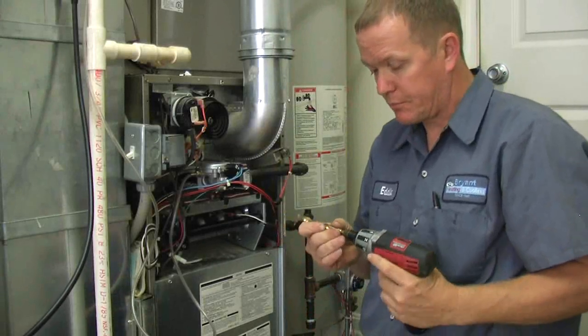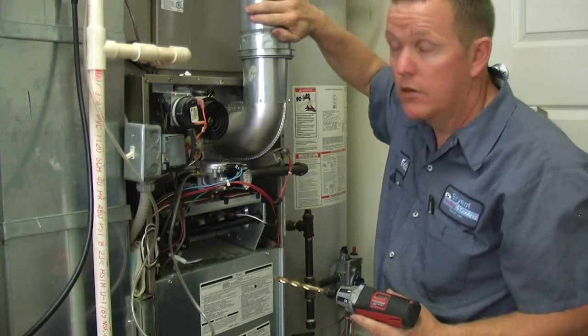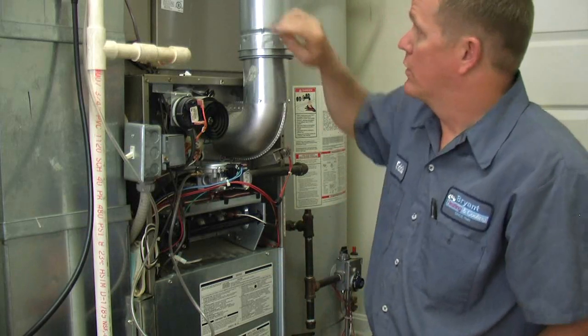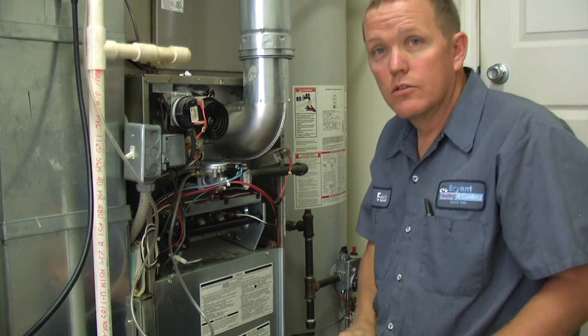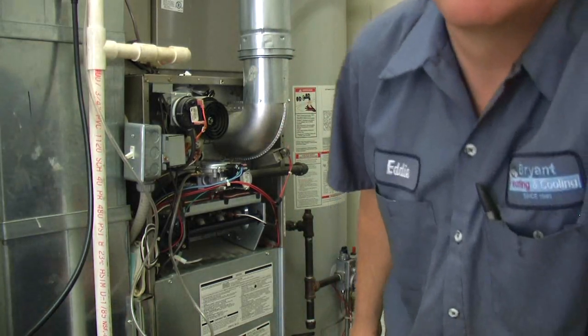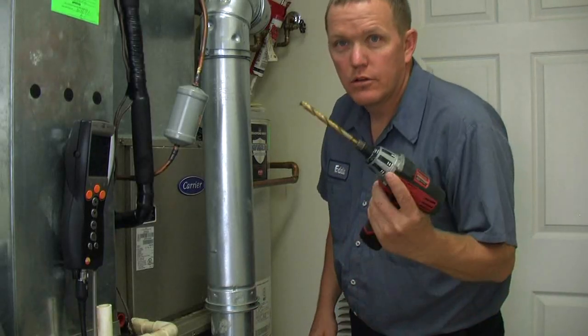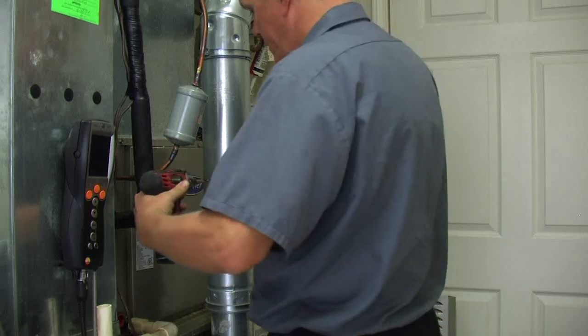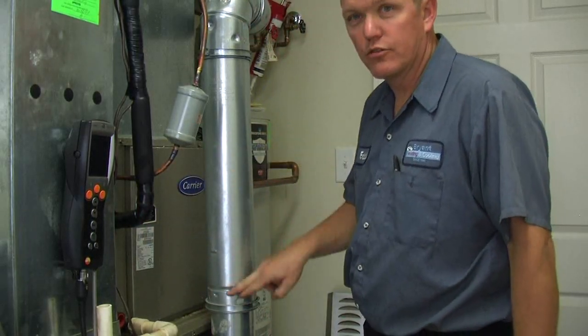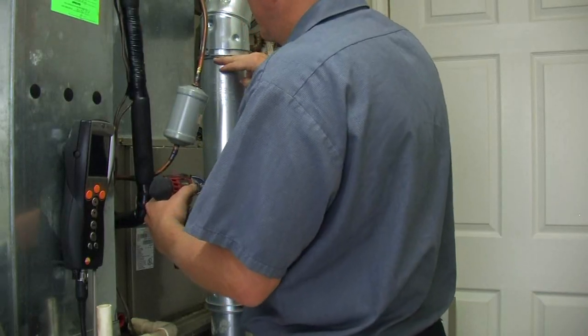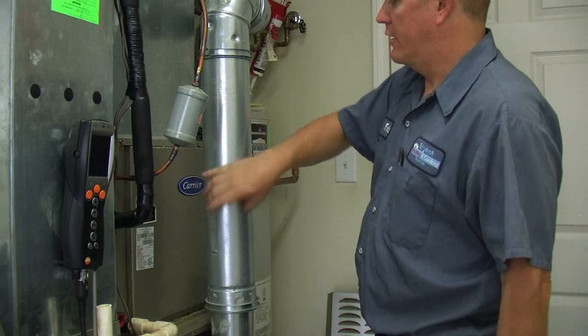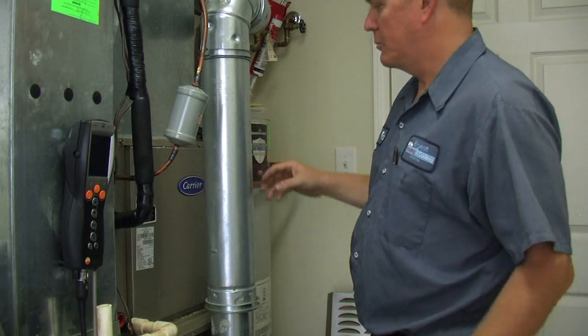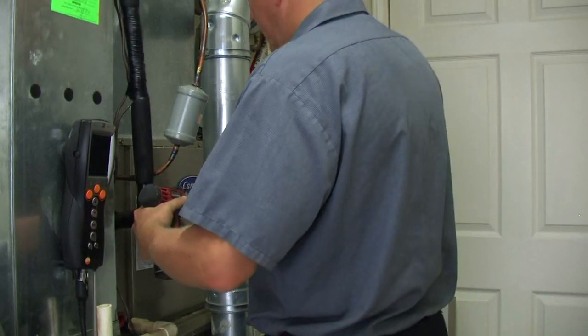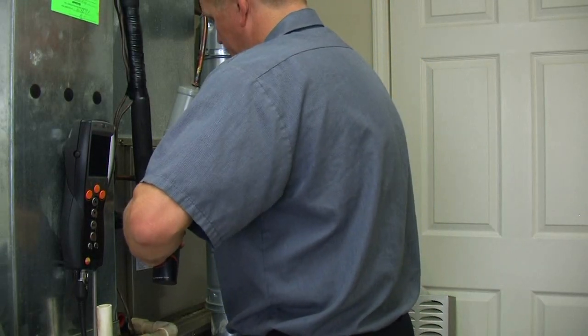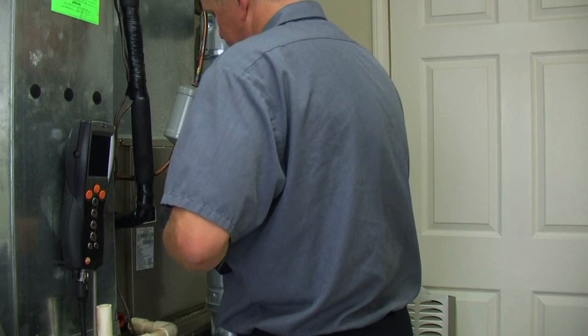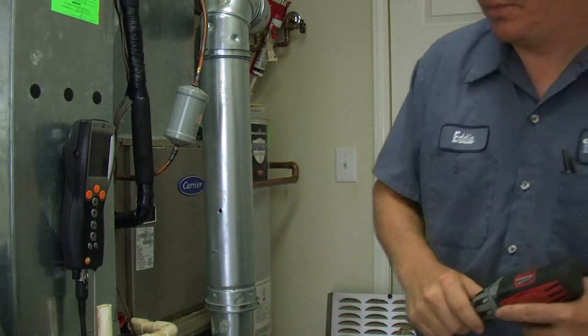Then I'm going to take my drill and we'll go ahead and drill me a hole through my B-vent here so I can stick the wand in there so I get my readings for the flue gases. So let me go ahead and do that now. Alright, so what I'm going to do is drill a hole right here. You want to try to get within the first 12 inches or so on your pipe. You want to be 12 inches or so below an elbow too. So if you got an elbow, you might want to come out within 12 inches past the elbow. Got a straight shot here, so I'm going to put it about right here. Alright, so there's my test hole.